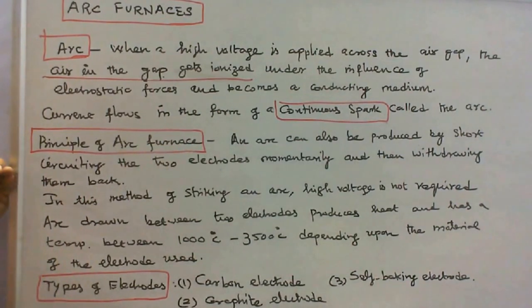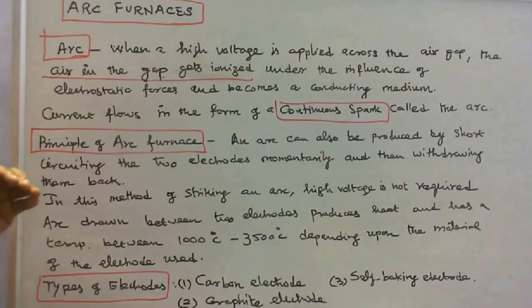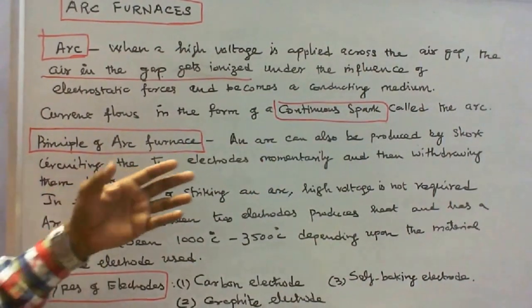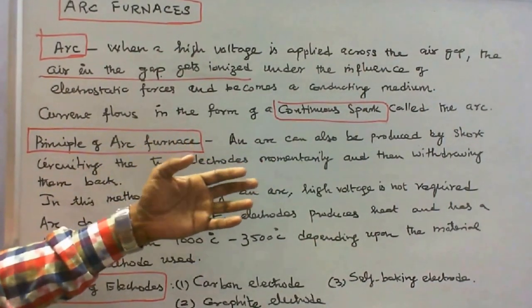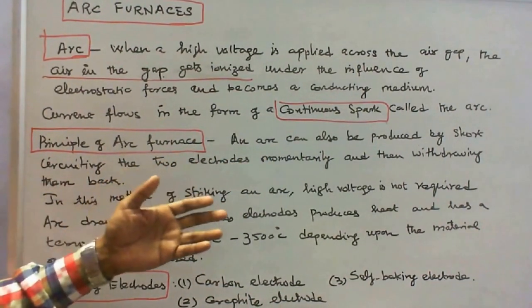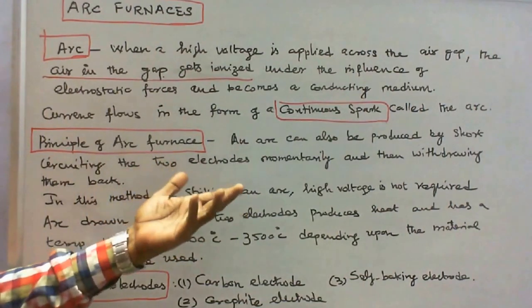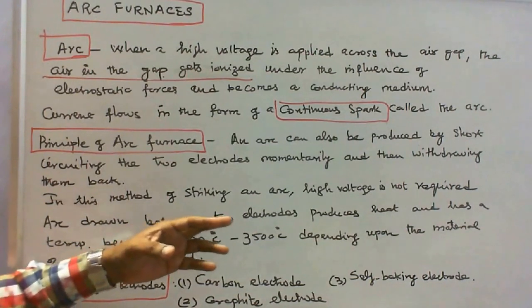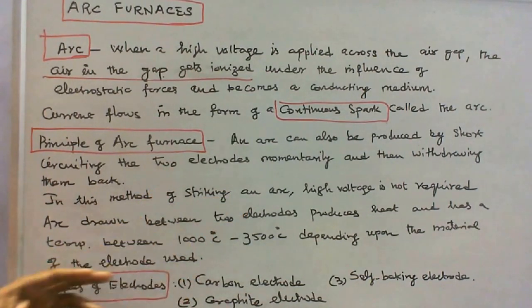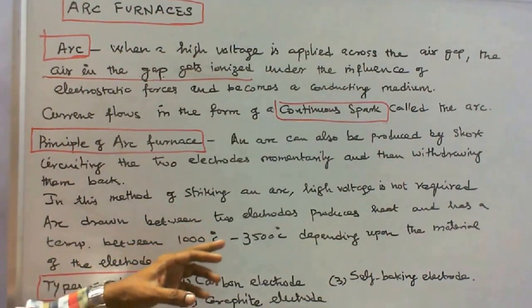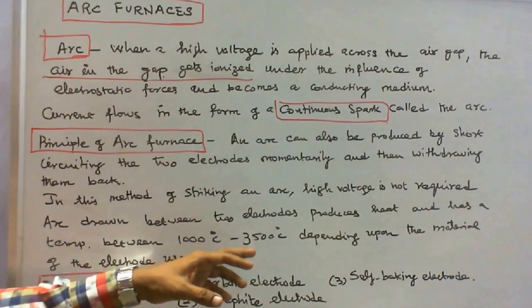What is the principle of arc furnace? An arc can also be produced by short circuiting the two electrodes momentarily and then withdrawing them back. In this method of striking an arc, high voltage is not required. An arc drawn between two electrodes produces heat and has a temperature between 1000 degrees centigrade to 3500 degrees centigrade, depending upon the material of the electrode used.